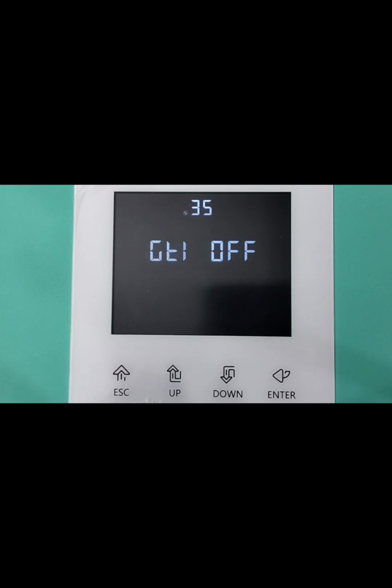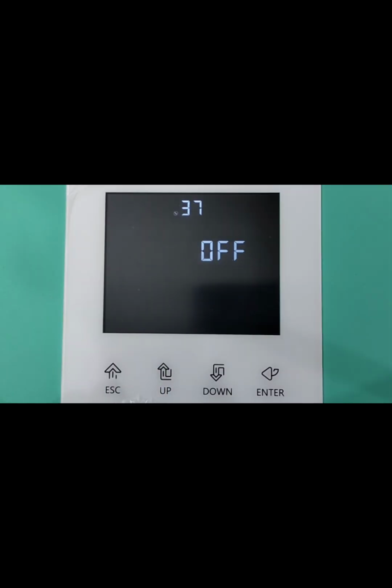Grid inverter function for feeding. Battery dual output shutdown voltage. Battery dual output duration timer. Option 38 for BMS communication, you have to turn on this. Option 39, low SOC shutdown function. Option 40, low SOC to main function.